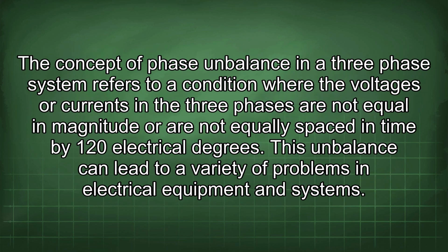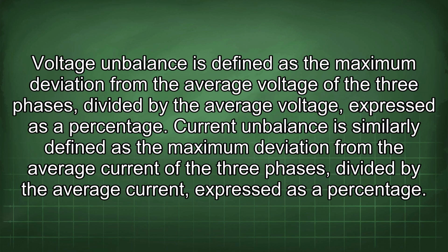The concept of phase imbalance in a three-phase system refers to a condition where the voltages or currents in the three phases are not equal in magnitude or are not equally spaced in time by 120 electrical degrees. This imbalance can lead to a variety of problems in electrical equipment and systems. Voltage imbalance is defined as the maximum deviation from the average voltage of the three phases divided by the average voltage expressed as a percentage. Current imbalance is similarly defined as the maximum deviation from the average current of the three phases divided by the average current expressed as a percentage.